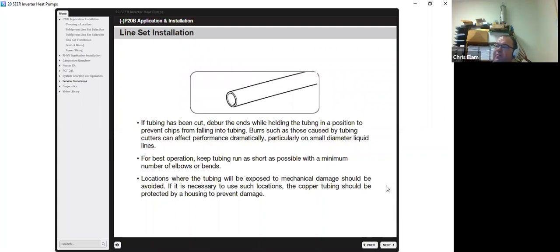If tubing is cut, be sure to deburr the ends while holding the tubing in position to prevent the chips from falling back into the tubing. Burrs such as that can affect the performance dramatically, particularly on small diameter lines. That can also stuff up your TXV or your EEVs. For best operation, keep the tubing as short as possible with the minimum number of elbows or bends. Locations where tubing will be exposed to mechanical damage should be avoided. If it is necessary to use such a location, the copper tubing should be protected by a housing to prevent damage.